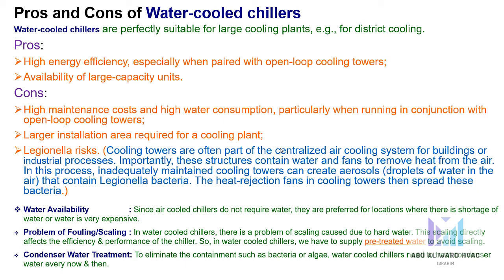And regarding the water availability, since air-cooled chillers do not require water, they are preferred for locations where there is a shortage of water or water is very expensive. Problem of fouling and scaling. In water-cooled chillers, there is a problem of scaling caused by hard water. This scaling directly affects the efficiency and performance of the chiller. So in water-cooled chillers, we have to supply pre-treated water to avoid scaling. Condenser water treatment to eliminate contaminants such as bacteria or algae. Water-cooled chillers need to treat condenser water every now and then.